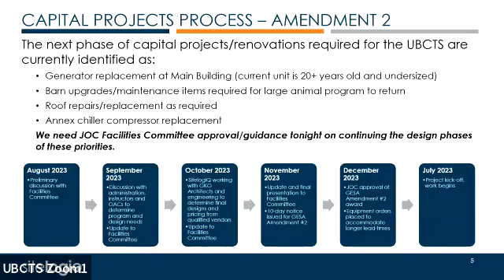On the generator, can we get away from propane? Yes, we are absolutely getting away from propane. We've already had this conversation. Propane, number one, is ridiculous right now. Diesel's more expensive though, I'm actually pricing the two out right now. For my work I need a 500 kW, that's why I'm so knowledgeable about generators right now. The diesel ones, the cost per hour running at 50, 80, and 100% load is like two and a half times what we have with natural gas. I would agree, if you guys had natural gas at this site there would be zero questions in my mind, you would want natural gas.